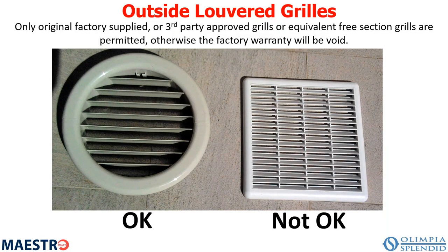We're very adamant about the fact that we have to be very careful in selecting the grills. As you can see here, the one on the left is the one that comes from the factory. The one on the right was used in an installation that proved unacceptable, because the free area you see on the grill on the left and the free area on the grill on the right are not equal — in fact, the one on the right is considerably less. That restricted airflow means capacity loss, depending on your mode of operation, high or low pressures. That's how we discovered this problem, the unit was having problems that others don't.